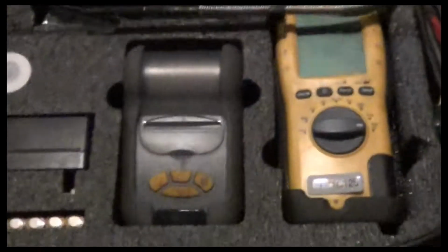So this is what I'm currently using. I've had this for quite a while. It does the job, it's got a printer, a dual port manometer, dual K-type couplers, and your flue sensor, where you can release the water from your condensate trap. The particle filters are in there too, and it does a nice job. Turn it on, it's going to zero itself out. You can see it zeroing, and it does everything everything else does. You've got your menu where you can put in your fuel type, flue test, pressure test, heat exchanger test, temperature test, room CO test.